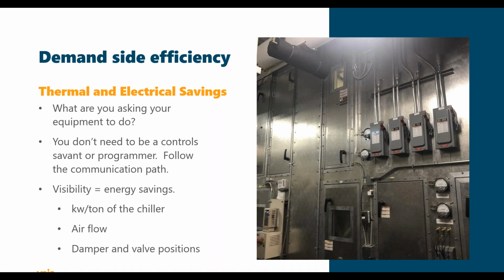Large complicated systems again have a lot of invisibility there, and I like to focus on the air handling units in a larger built-up system and how those are demanding energy from the central heating and cooling plant, then focus on the space and how that's demanding energy from the air handler. Looking at an air handler could be interesting, but it isn't going to tell you much about the potential for that customer to optimize their energy use.